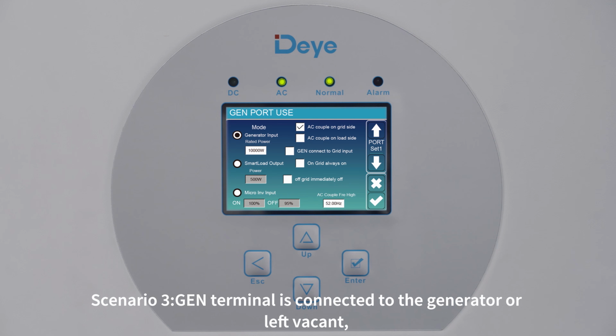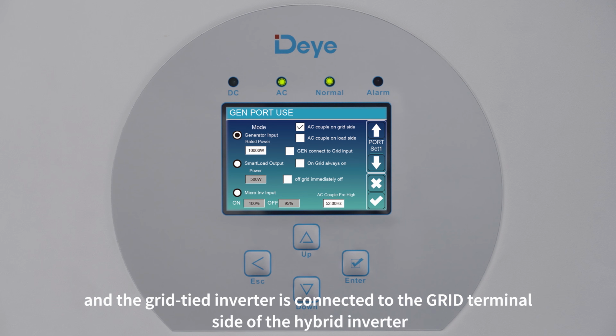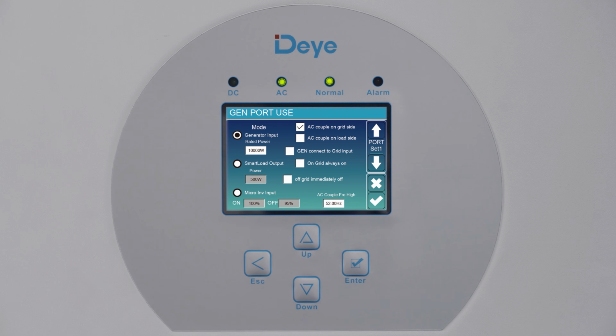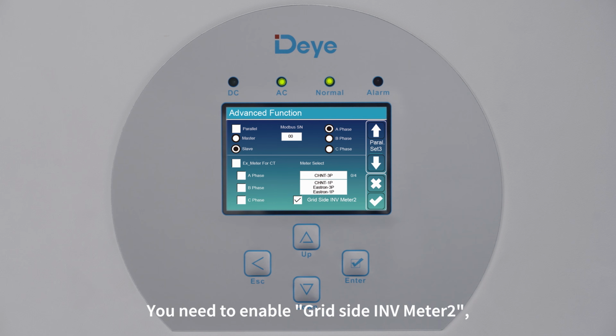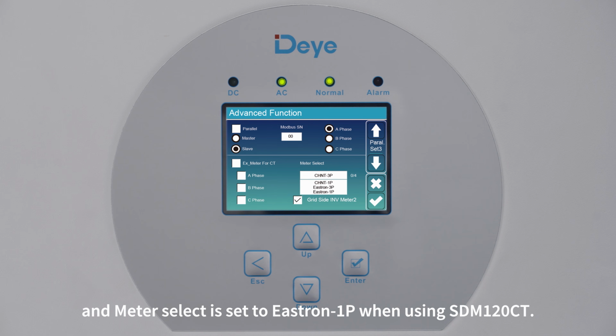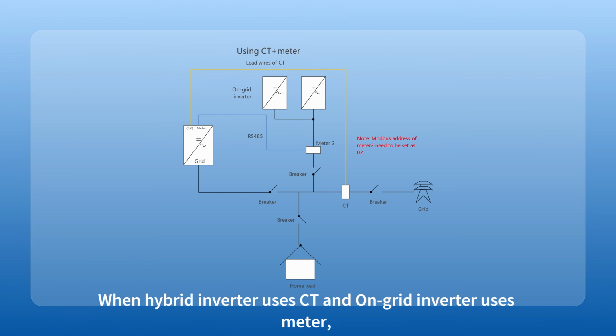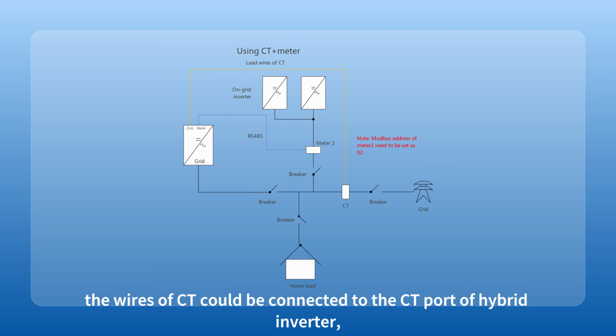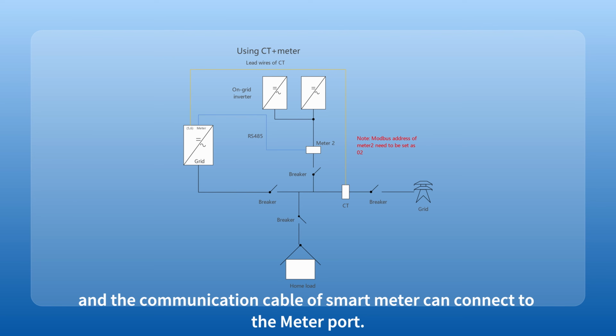Scenario 3. The GEN terminal is connected to the generator or left vacant, and the grid-tied inverter is connected to the grid terminal side of the hybrid inverter. You need to enable Grid side INV Meter2, and meter select is set to Eastron-1P when using SDM120CT. When the hybrid inverter uses CT and the on-grid inverter uses a meter, the wires of the CT can be connected to the CT port of the hybrid inverter, and the communication cable of the smart meter can connect to the meter port.